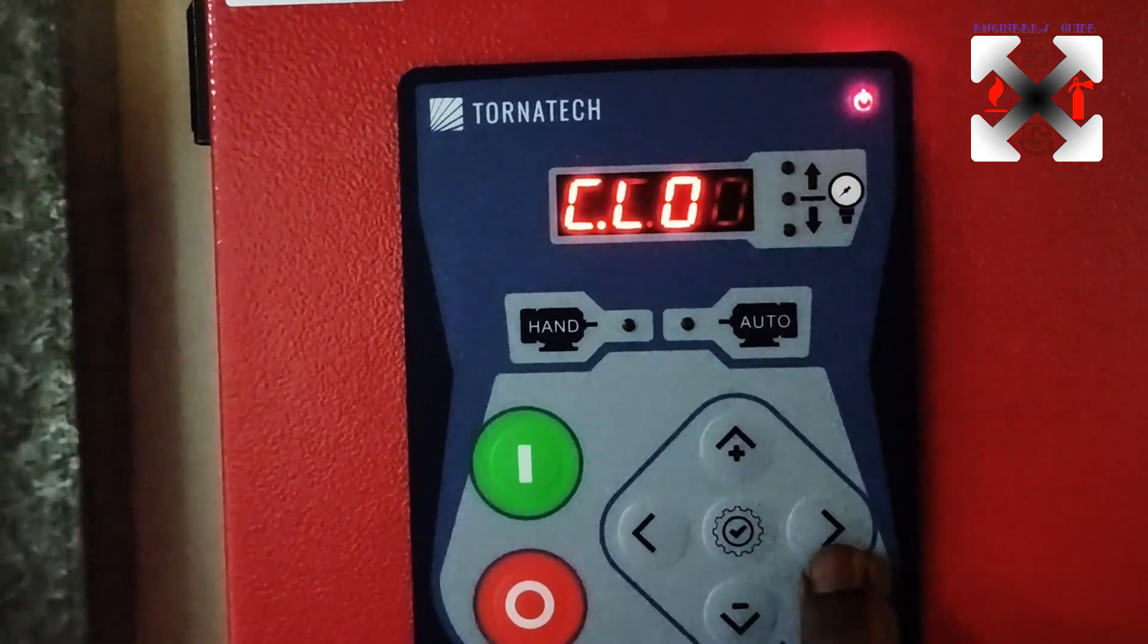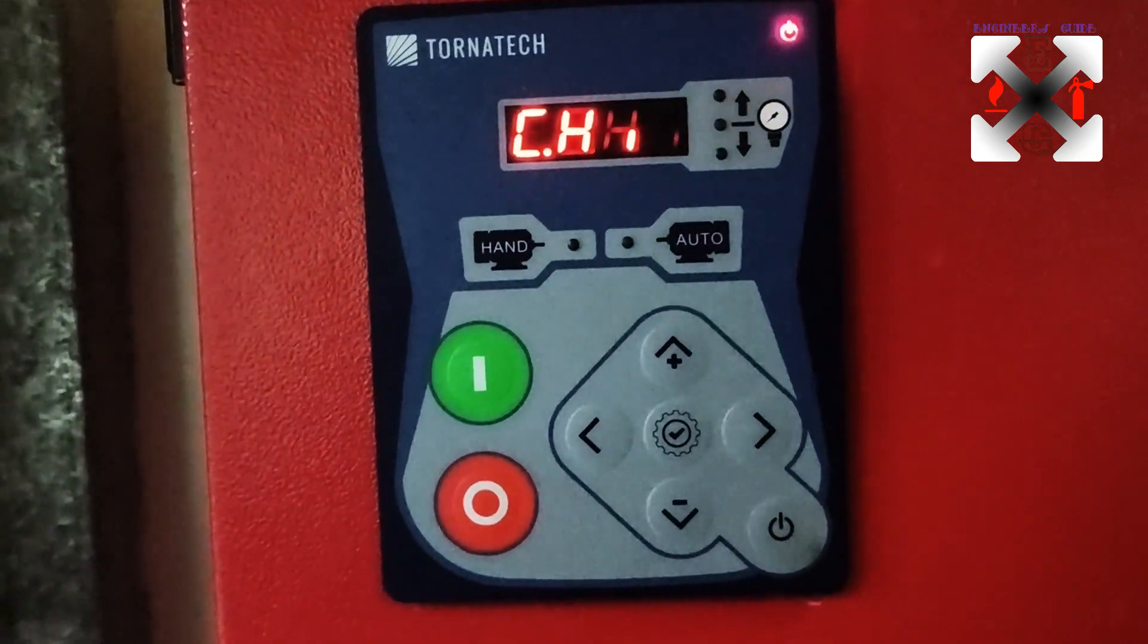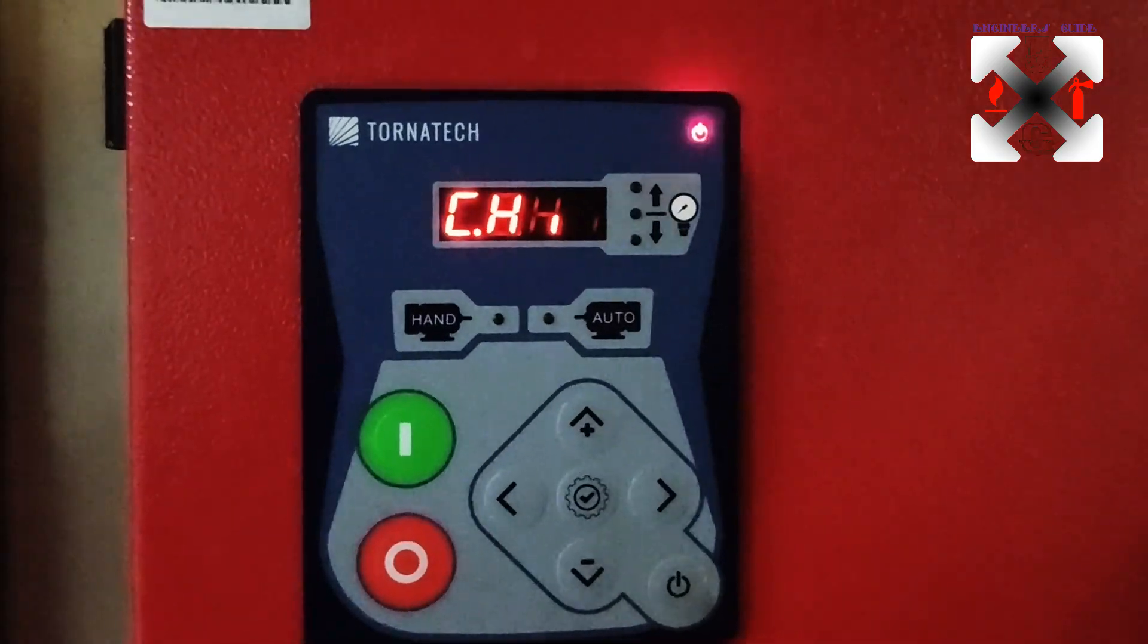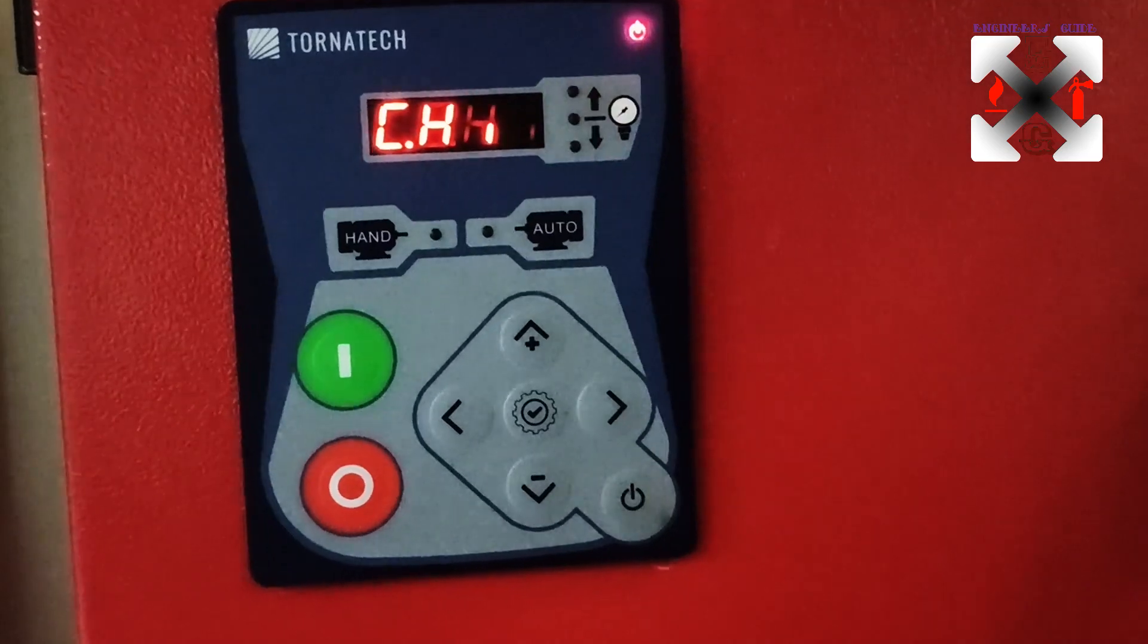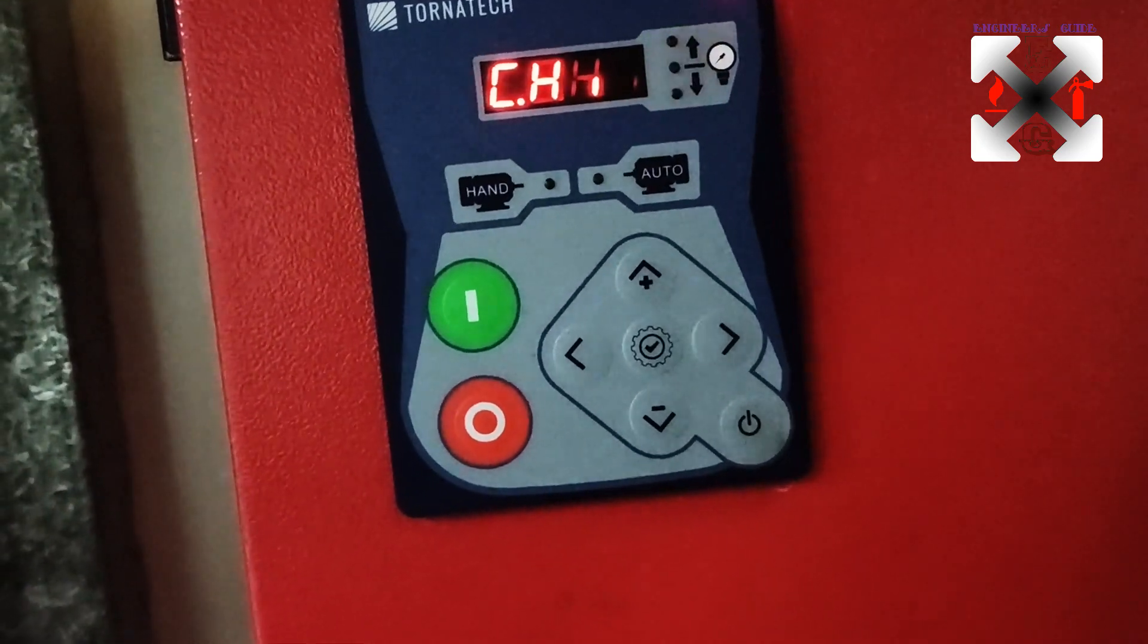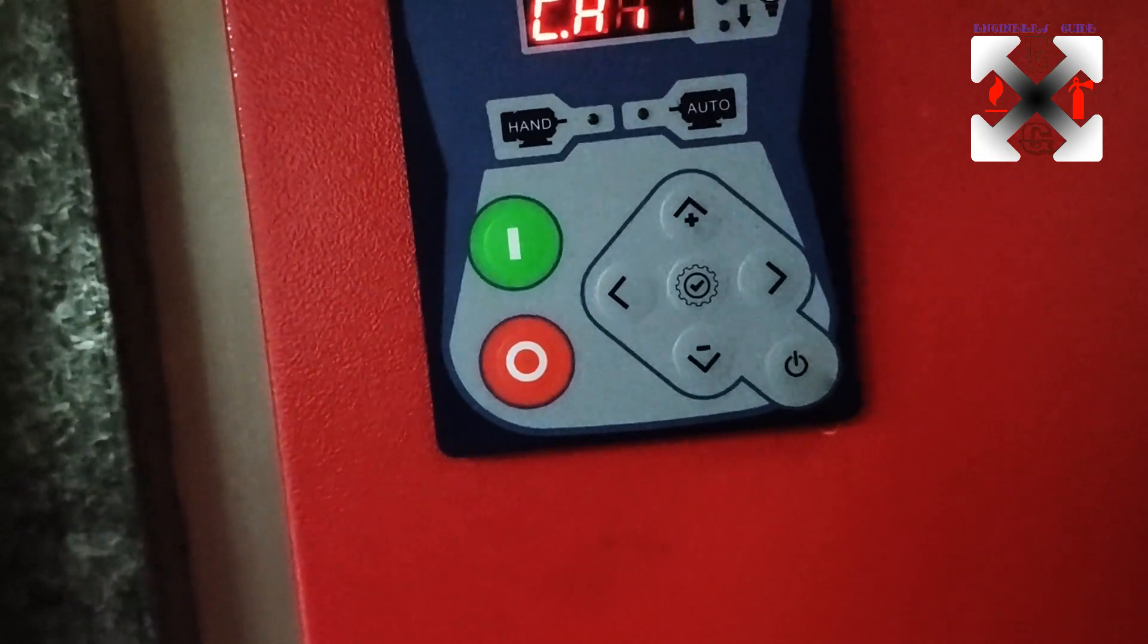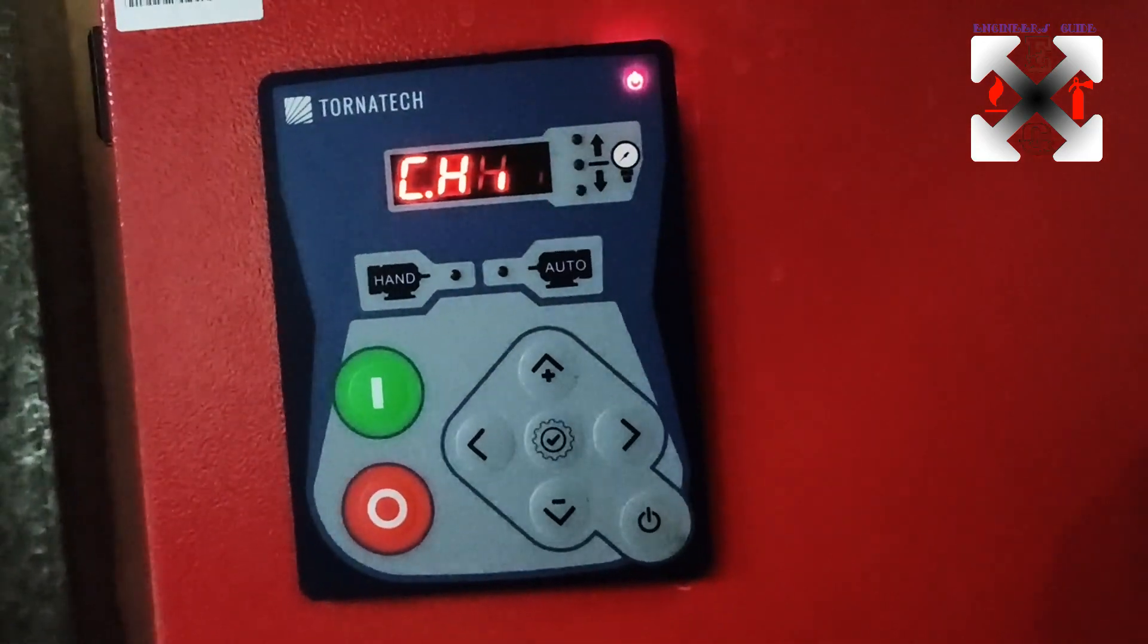Then after you press forward, this calibrates the high pressure. How do you do this one now? Now that you have drained the system, you will start the pump - the electric pump - and pressurize it till the maximum. All the valves have been closed, you pressurize.